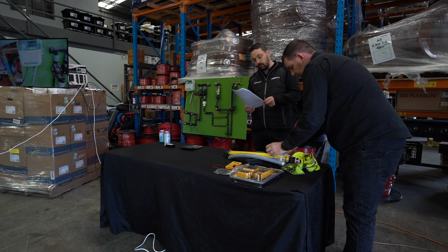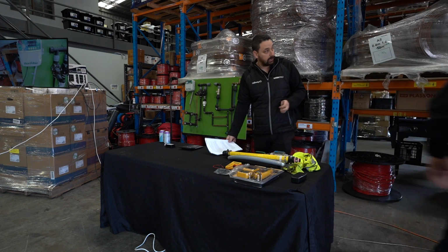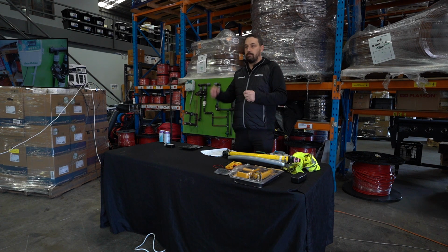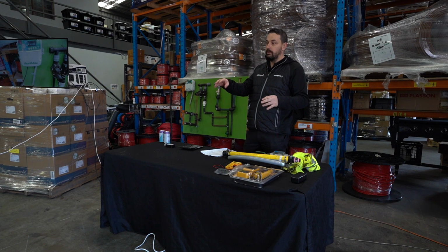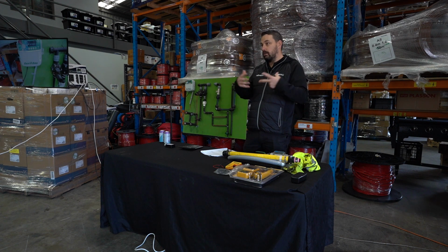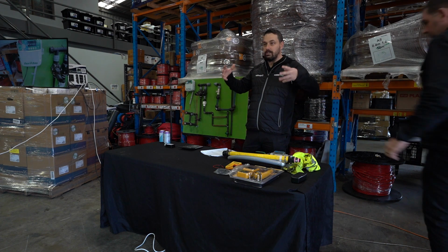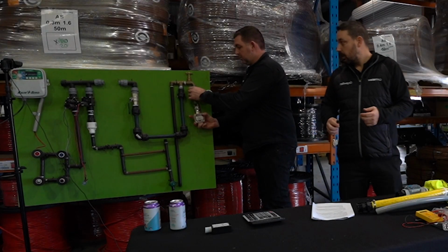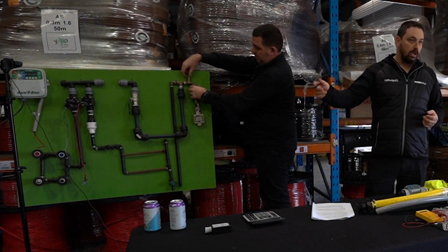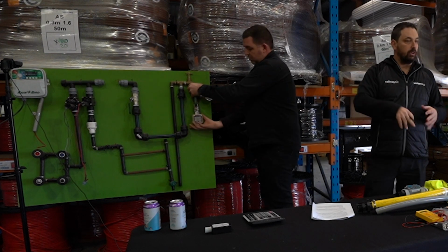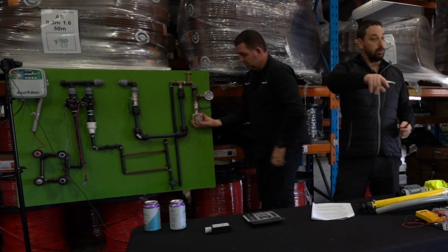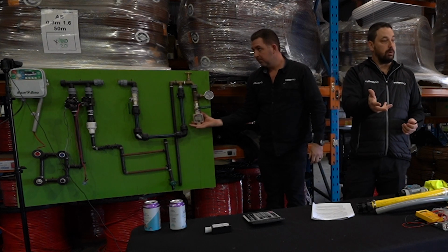The next side of things is obviously static pressure. When we talk about static pressure, we are talking about the pressure with no water movement. So that's obviously at a static standstill point. What we would do there is, as Clint's showing you here, at a tap or at a backflow, if you know your system's off, you can screw this pressure gauge into a test point on one of the backflows and be able to get a pressure off of that.